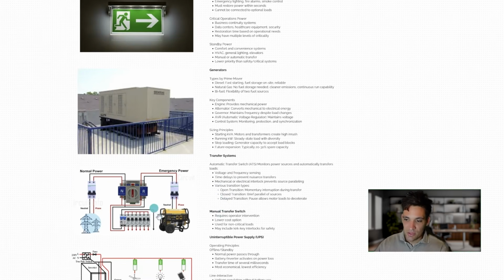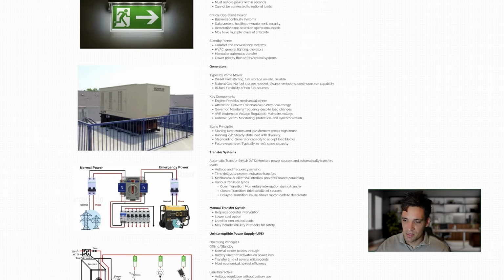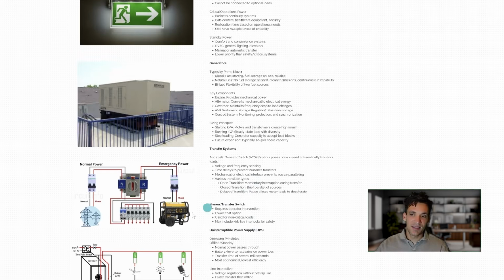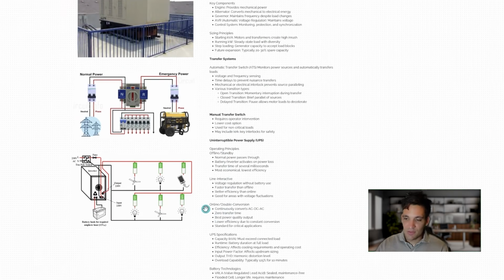If you look at this wiring diagram here, you can see in normal state, there's normal power connected to the grid, and then there's an emergency backup generator. So when the power drops out, you flick the transfer switch, or you can get automatic transfer switches that operate automatically, where you switch from the normal power to the emergency power to power your system. These can be automatic, sensing when the voltage drops out, flicking on the generator and switching to the emergency power, or you can have a manual transfer switch which requires a person to go and operate them.